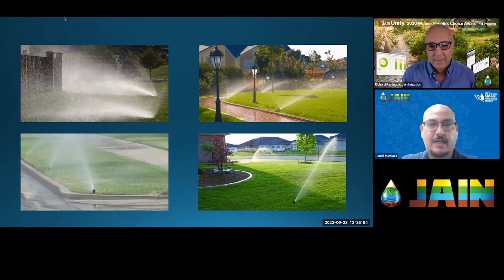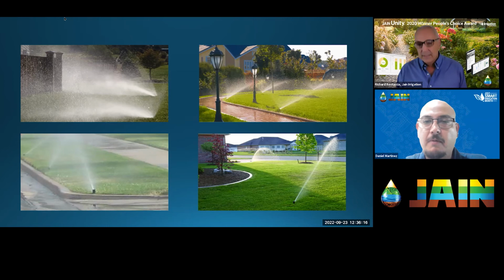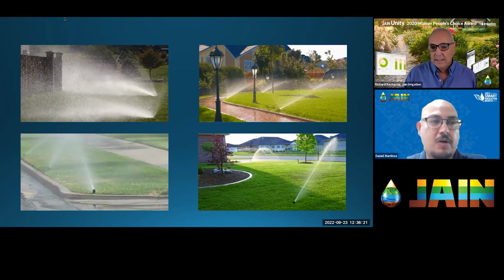Absolutely, Richard. We come across this. Literally, I was out on a site this Monday and spotted it right away with the contractor. He has a new site that they just took over. I showed them how to adjust their valves to eliminate this. So what we want to see in a sprinkler system is not what you see on the left: all the misting, all the water blown away from the system having too much pressure. What we want to see is what you have on the right side there. The top one, spray heads, nice big water droplets, minimal misting. The bottom rotor, you see a nice sharp stream rotating back and forth. You don't see all that mist again.